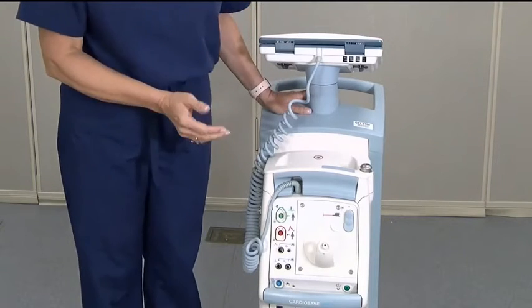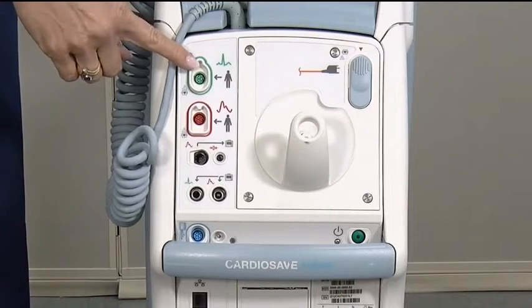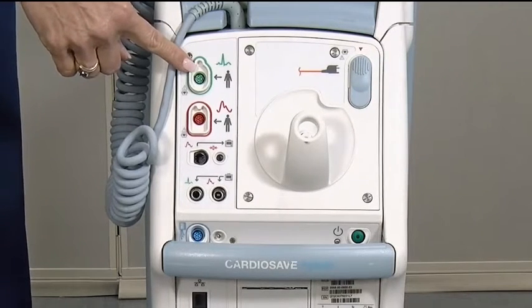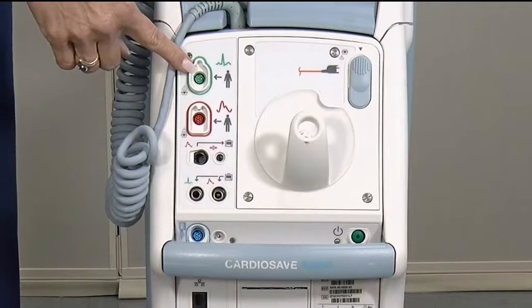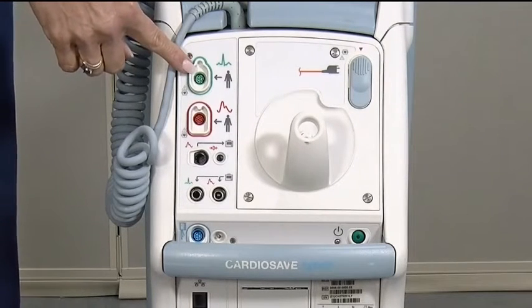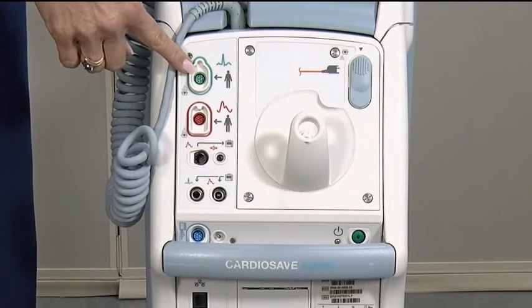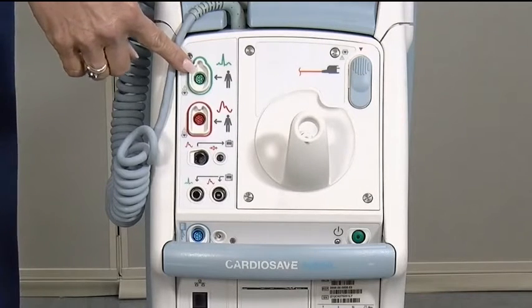The back of the pump is where all the connections are made. When you start at the very top, this is the ECG input. The ECG input is specific to the CardioSave balloon pump, and the cable that goes in there will not fit in any other pump, nor will any other ECG cable fit in the CardioSave balloon pump.